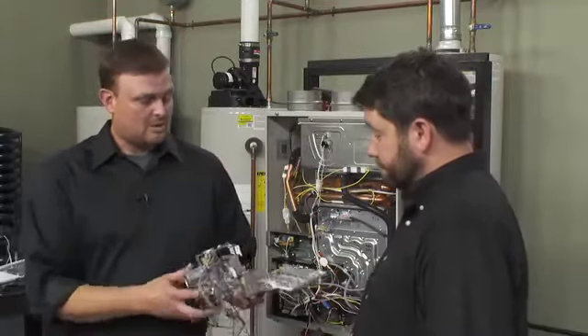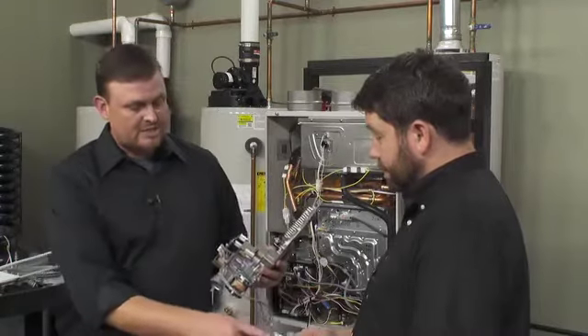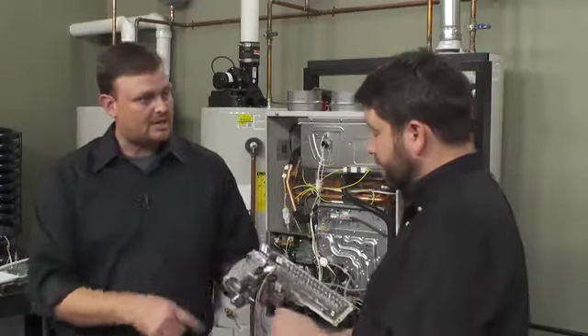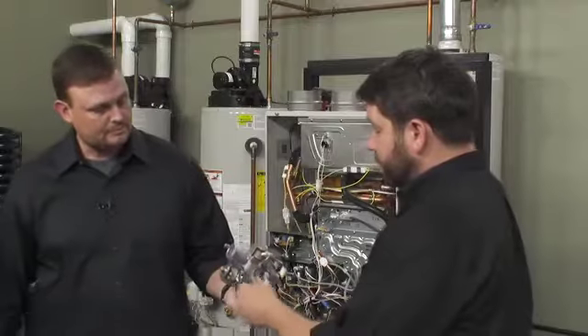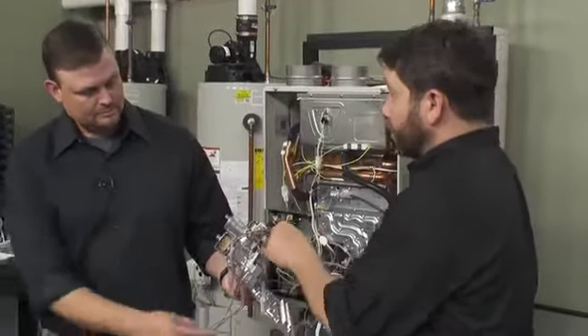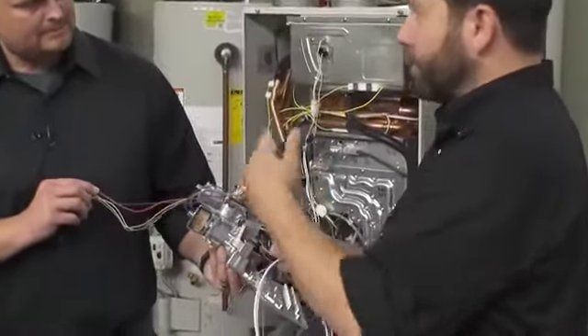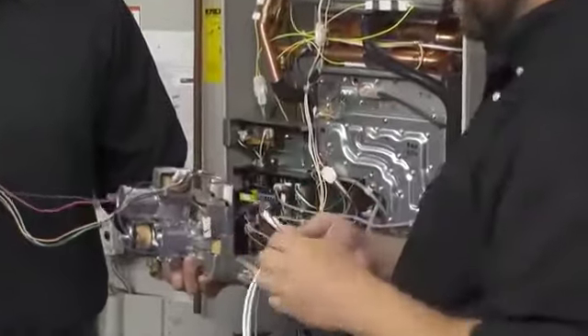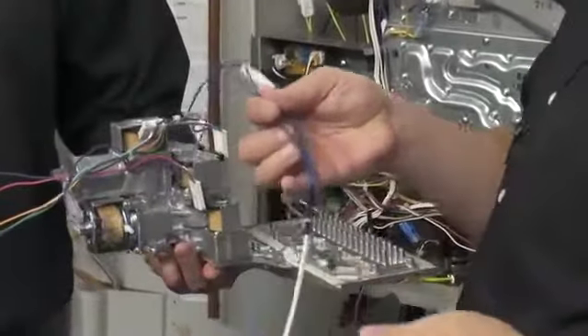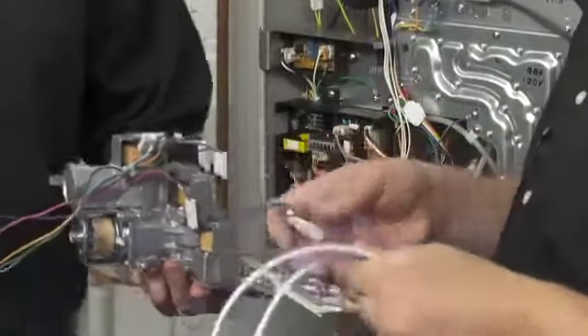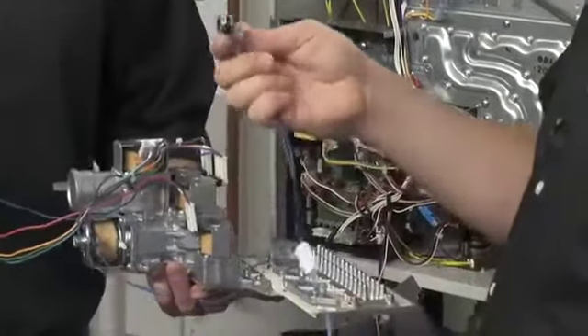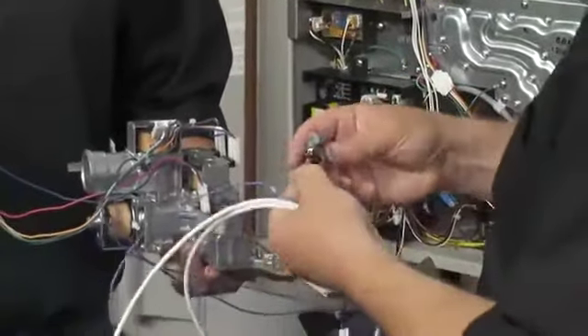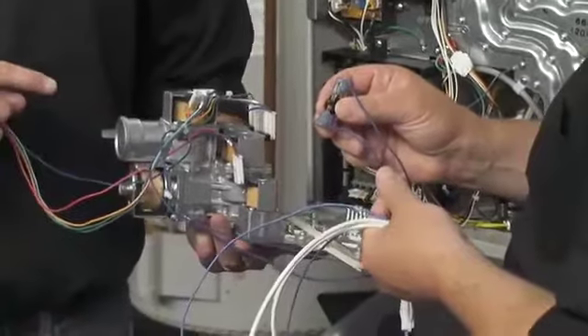Right. Now you're saying that the safeties are actually tied into the gas valve. Yeah, you'll see all of the gas valve solenoids have a blue common wire. Right. So that's what lets the power flow through and actually energizes the solenoid. So all of those commons go through our 2 safeties here. Right. And they're wired in series. So we've got our push button high limit. That's our manual reset.